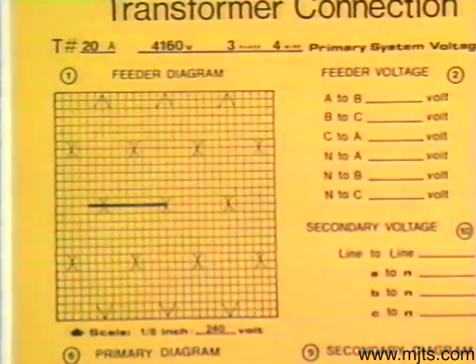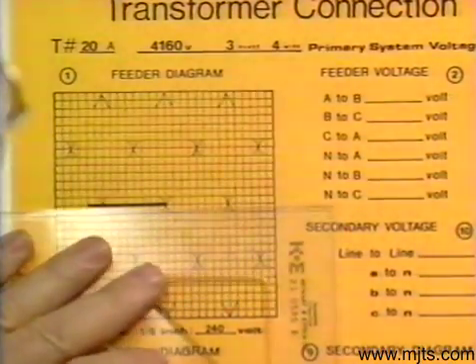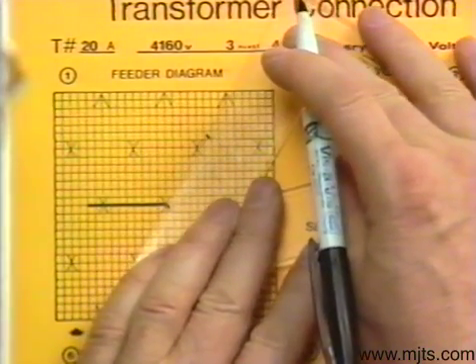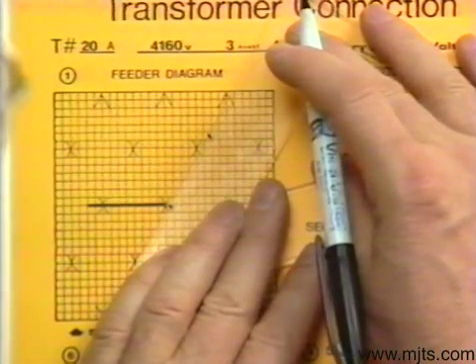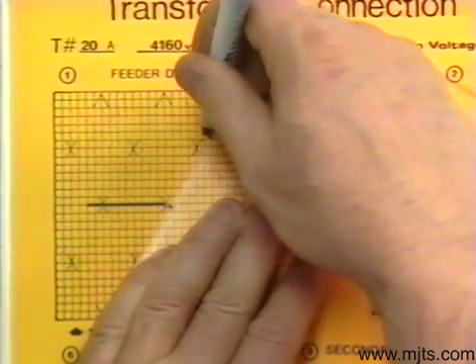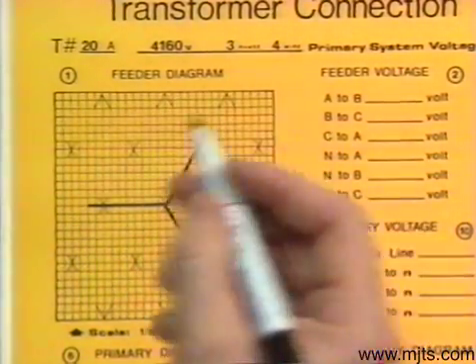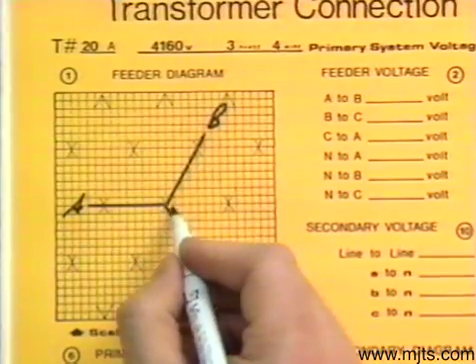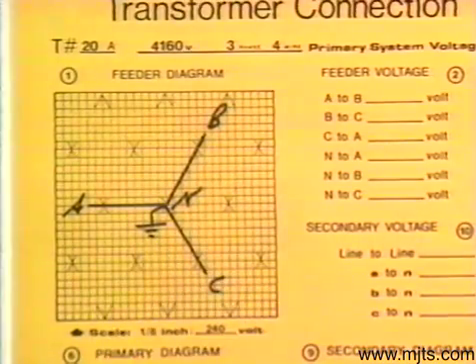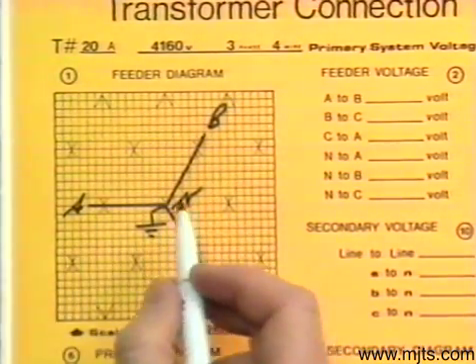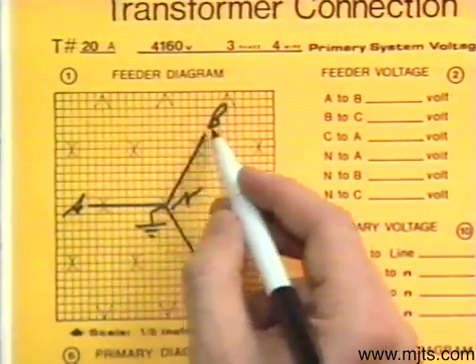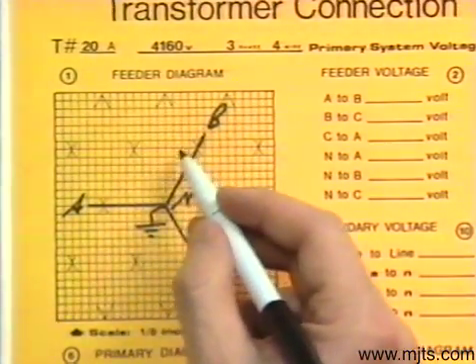We'll measure those out and mark each for 2400 volts. Using crosses to make it easier, we draw in our vectors and label them for phase — A, B, C in uppercase letters. The neutral is in the center, and we ground the center. Each of those vectors represents 2400 volts, and between phases the system voltage, the phase-to-phase value, is 4160.